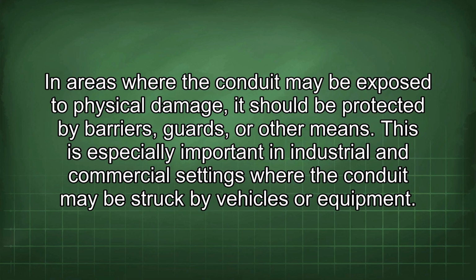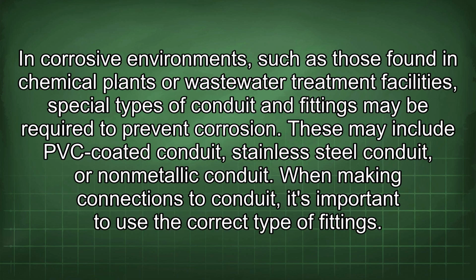In areas where the conduit may be exposed to physical damage, it should be protected by barriers, guards, or other means. This is especially important in industrial and commercial settings where the conduit may be struck by vehicles or equipment. In corrosive environments, such as those found in chemical plants or wastewater treatment facilities, special types of conduit and fittings may be required to prevent corrosion. These may include PVC-coated conduit, stainless steel conduit, or non-metallic conduit.